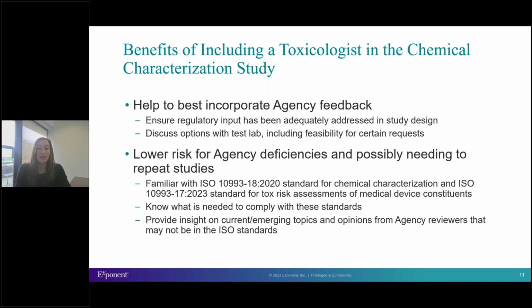I'm working on a project right now with chemists at Eurofins EAG, where the agency has asked for gas pathway testing for volatile organic compounds, VOCs, via the standard ISO 18562. Specifically, they want it for a known additive that's applied to the outer surface of the device. However, I've done my research on it. The chemical's not volatile and it's not expected to leave the surface of the device. It's a very large molecular weight, non-volatile compound.